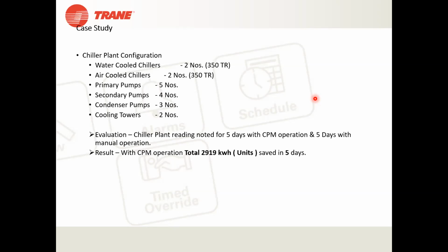This is the technical point. Now let's think about the commercial point of view. If you use an air cooled chiller, your electricity bill will be around 0.9 to 1 kilowatt per ton, maybe up to 1.4 kilowatt per ton maximum. But if you use a water cooled chiller at the same place, it's 0.45 kilowatt per ton, up to 0.6 or 0.7 kilowatt per ton maximum. So that way you are saving on electricity bills.